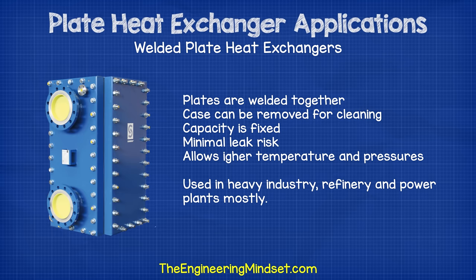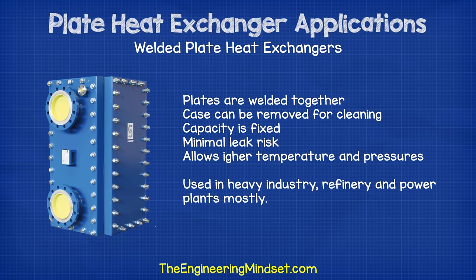There's a variation called the welded plate and frame heat exchanger. In this type, the plates are all welded together in one block, so they cannot be dismantled and the heating and cooling capacity is fixed. However, they allow for much higher pressure and temperature fluids to be used and minimize the risk of leakage, so hazardous fluids can be used. You'll find these mostly in heavy industrial sites, power plants, and oil refinery applications.